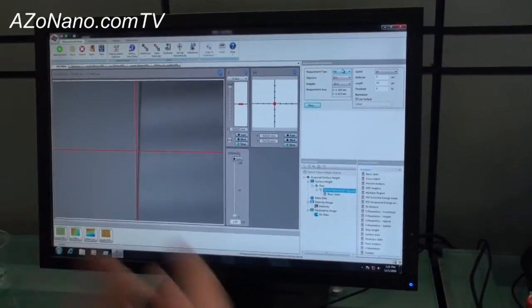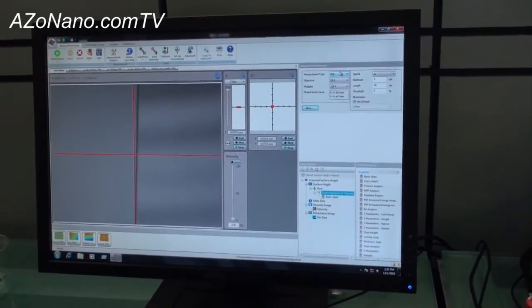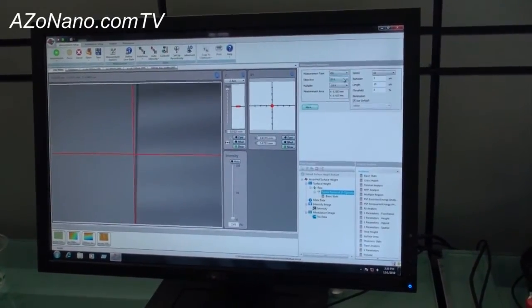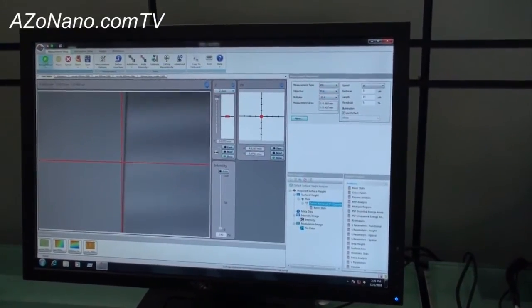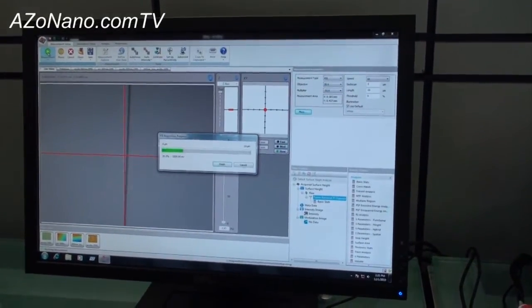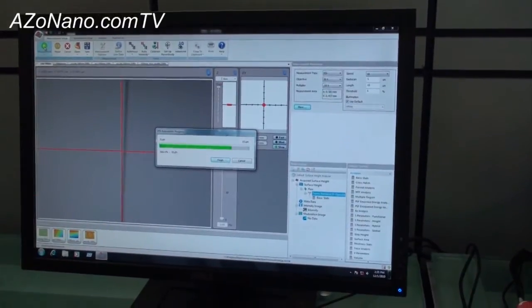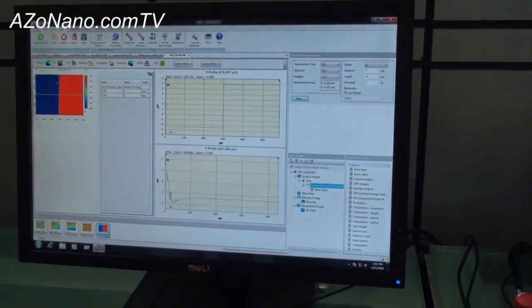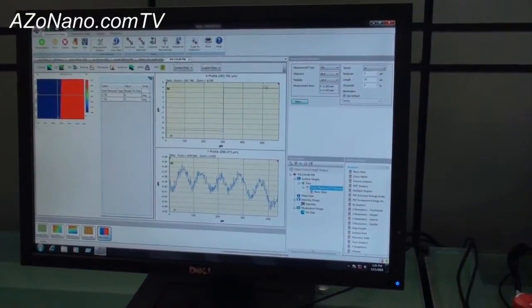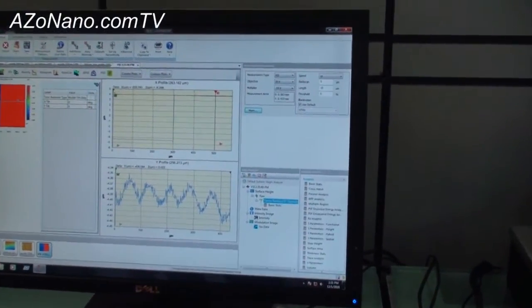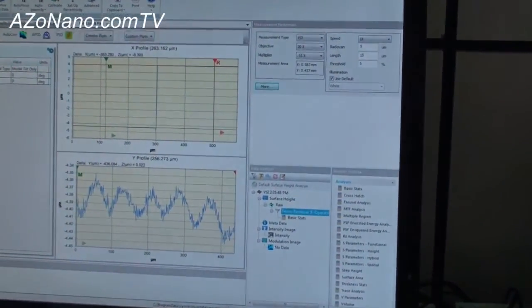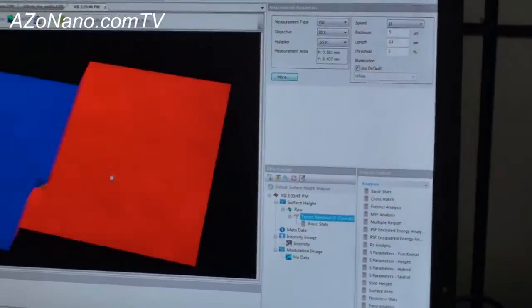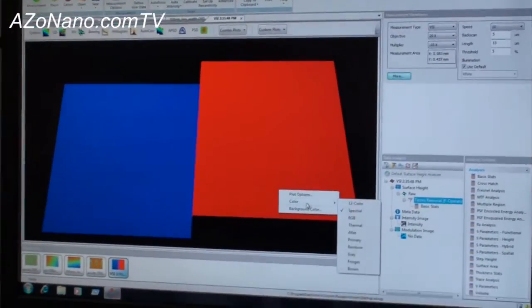We'll talk about some other techniques to get us down to the angstrom level measurements. But all I'm going to do is select VSI measurement, select which objective and hit measurement. Now you'll see the fringes scan through the top surface and bottom surface. Here's our step and here's a 2D cross-section. We can get our step height profile. Then we can do other things in here like look at this in 3D and rotate it around and look at the surface.